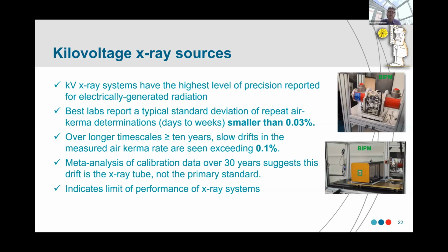And then over longer timescales, over a decade, slow drifts may be only 0.1%. BIPM have got perhaps the most comprehensive data that I've seen, suggesting that that sort of drift of 0.1% is actually the tube output, not the standard, and that perhaps indicates the limited performance of X-ray systems.